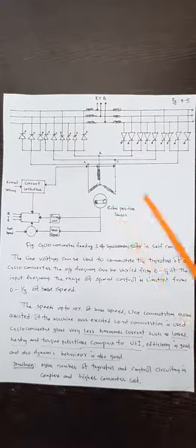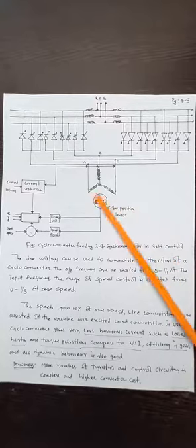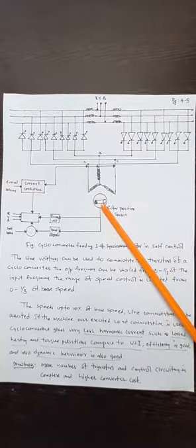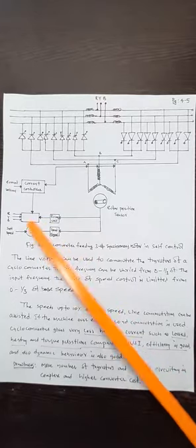So the rotor position sensor is to be placed here, otherwise voltage sensors. So see, the speed is sensed, and that set speed is to be compared with the actual speed of the motor, and you can generate the firing unit. So this firing unit gives the pulses for all the 18 thyristors.